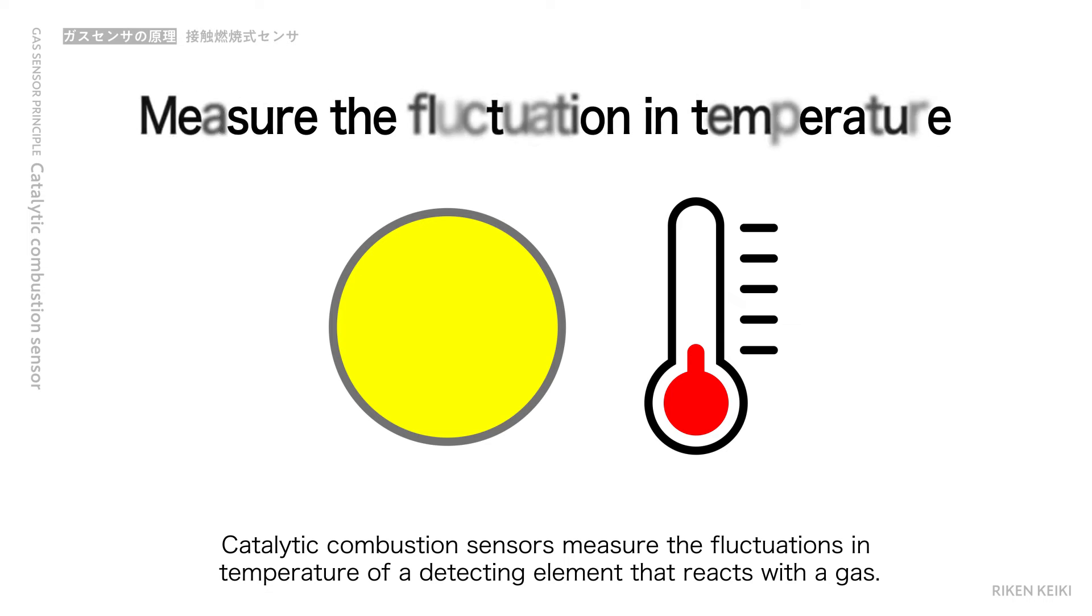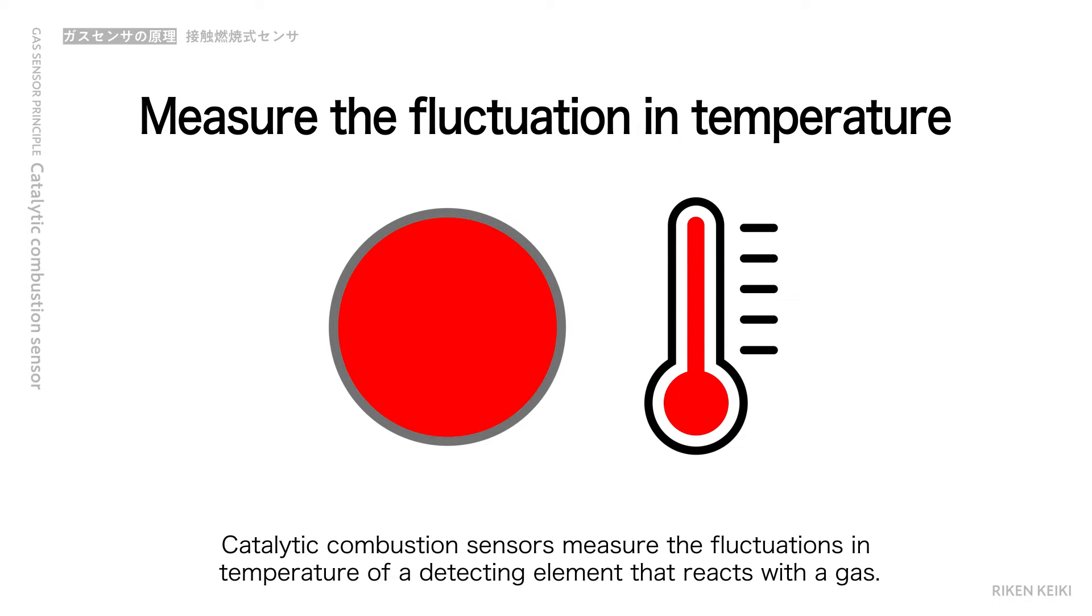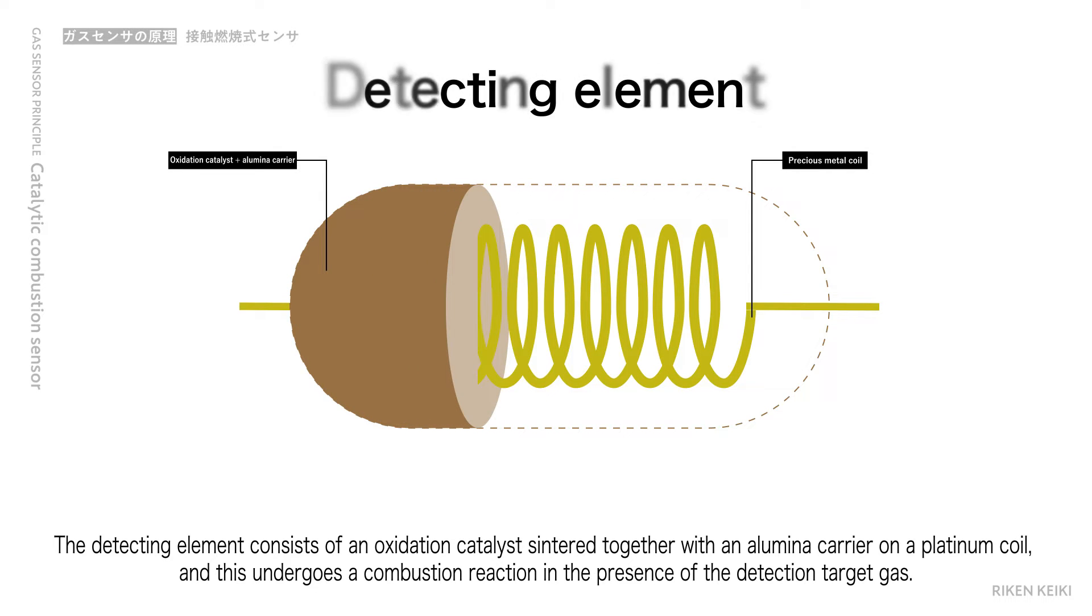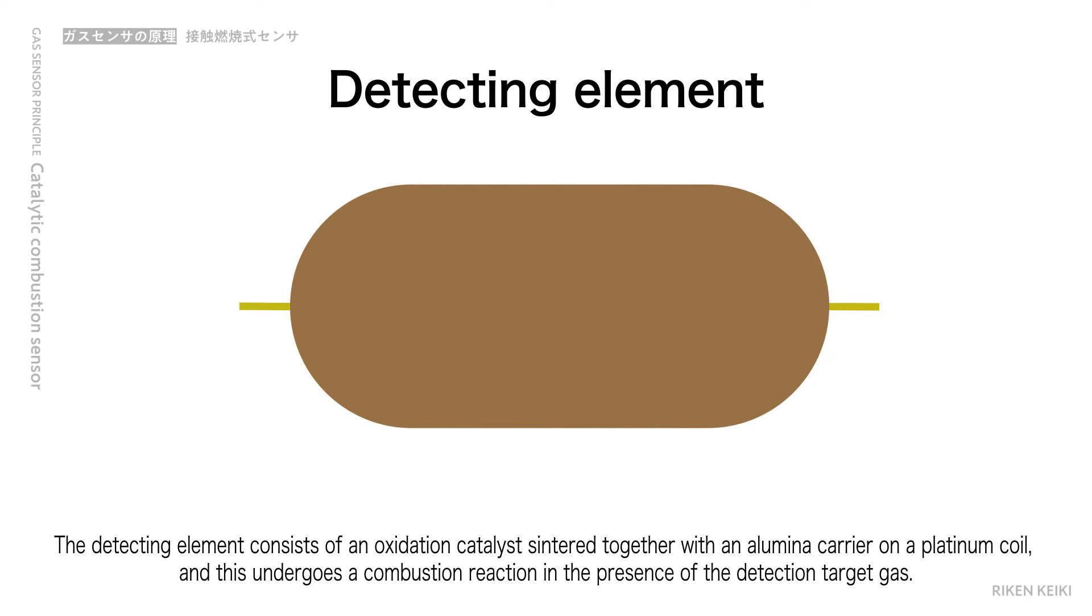Catalytic combustion sensors measure the fluctuations in temperature of a detecting element that reacts with the gas. The detecting element consists of an oxidation catalyst sintered together with an alumina carrier on a platinum coil, and this undergoes a combustion reaction in the presence of the detection target gas.